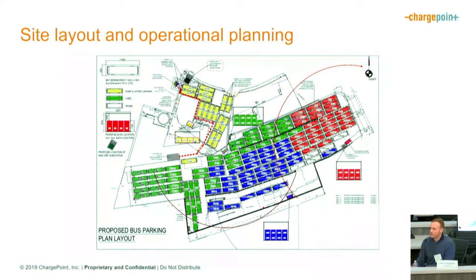Another challenge is that each of the buses are double deckers, so they're a little taller than most buses. Tying back to the red ring, we have little clusters of charging stations, the red block, the blue block on the bottom, and another red block to the left. Those are strategic points where we have switchgear and converters sitting in areas mapped out on the DC side into these color-coded zones.